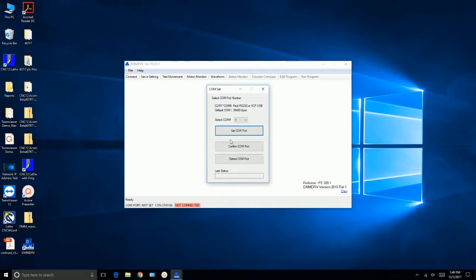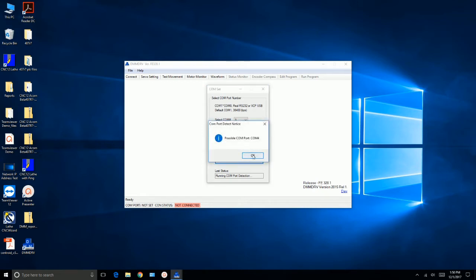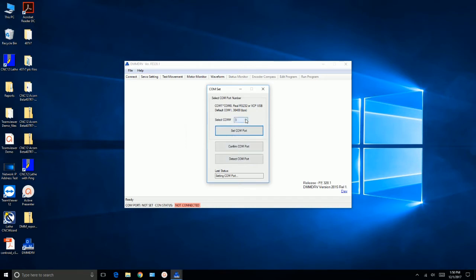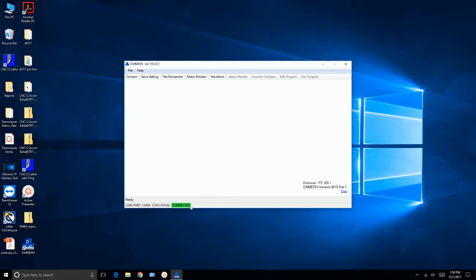And since we don't know which USB port we're on, we click on detect COM port. And it says possible COM port 3 and possible COM port 4. So let's go up here and try COM port 3 first. Try and set it. So it says error communicating with a servo drive. So let's go ahead and try COM port 4. And let's set the COM port. COM port successful. Then you see down here it's connected.